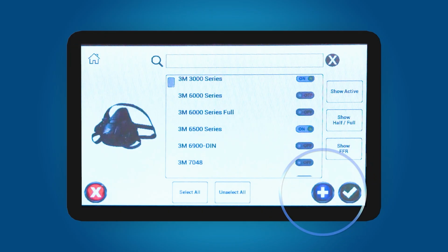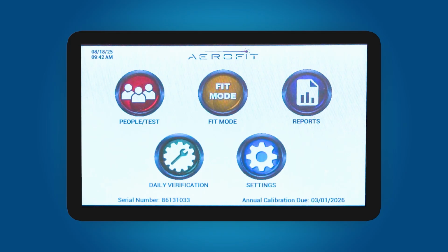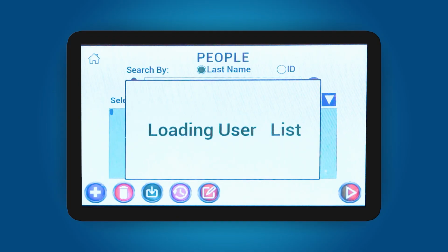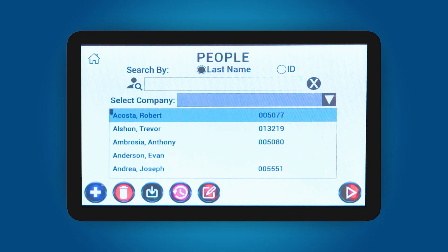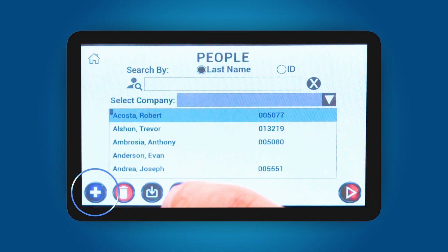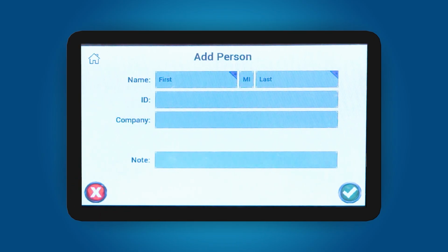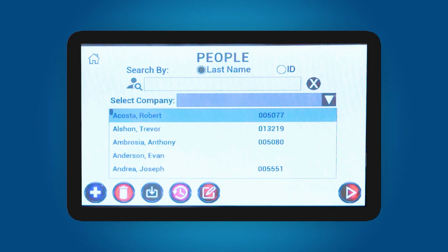Adding respirators can be done using the purple plus sign. Be sure to confirm the respirator type is accurate, as it will determine the fit factor and other settings during testing. Now, to add people or test subjects, select the red People Test button at the top left of the home screen. Within this screen, you can import test subjects, delete, or add new test subjects. To add a new test subject, simply press the purple plus sign at the bottom left of the screen. Enter the person's information with first and last name being required. Notes can be added for the record as well.